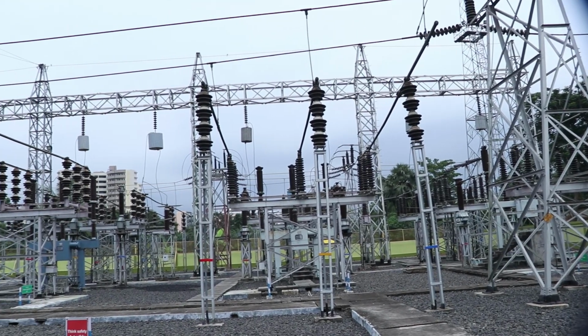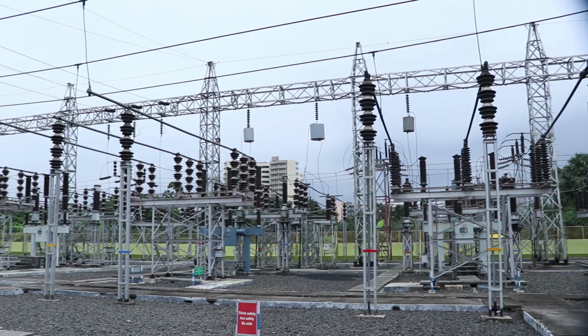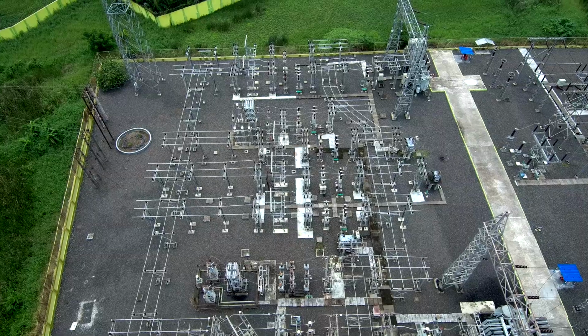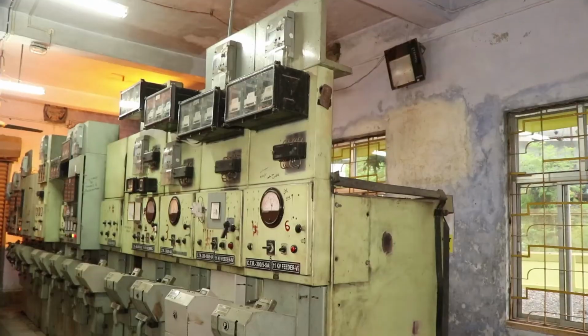The substation is one of the oldest substations of the company. It provides power to consumers through 33 kV and 11 kV feeders. Mainly we receive power from Lakshmikantapur 220 kV substation through Falta double circuit and Sherakol single circuit. Then it is stepped down to 33 kV level via 132 by 33 kV transformers and 11 kV level via 33 by 11 kV transformers. This substation operates at three voltage levels: 132 kV, 33 kV and 11 kV.